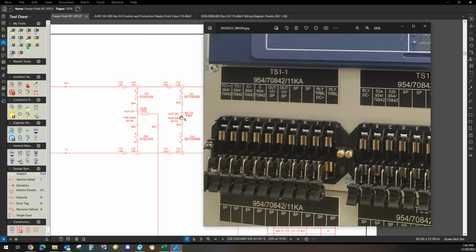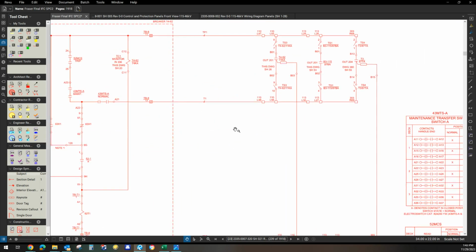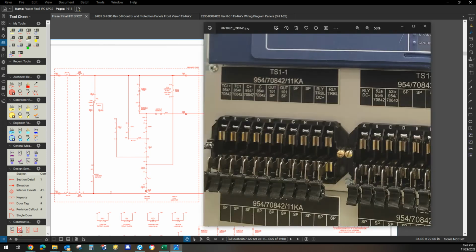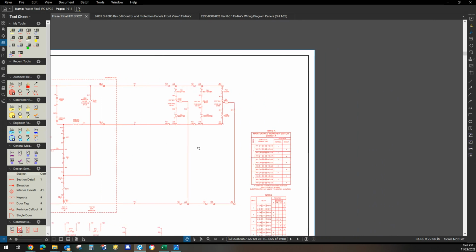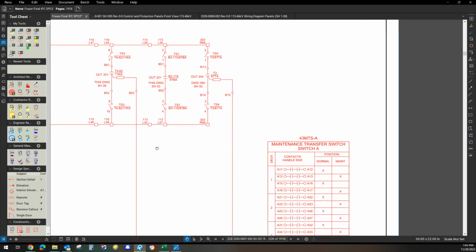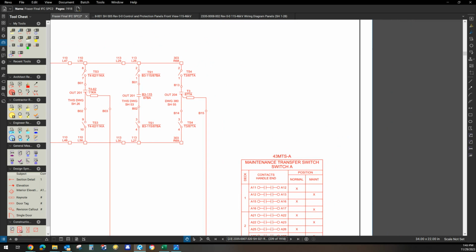And if that contact is closed, that means I have a standing trip. And if I close this finger, which is 3, with a standing trip, I'm going to send the trip down, and it's going to trip the breaker. This is a key fundamental to understand. And this happens, guys. This happens in the field more than you would believe.